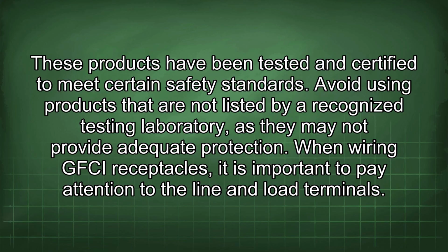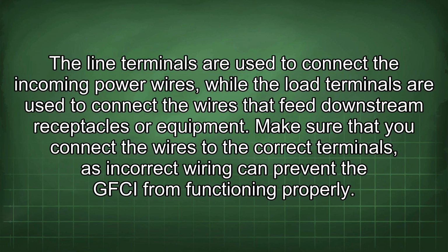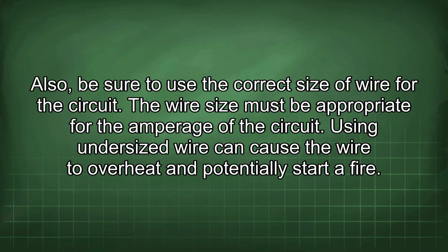When wiring GFCI receptacles, it is important to pay attention to the line and load terminals. The line terminals are used to connect the incoming power wires, while the load terminals are used to connect the wires that feed downstream receptacles or equipment. Make sure that you connect the wires to the correct terminals, as incorrect wiring can prevent the GFCI from functioning properly. Also, be sure to use the correct size of wire for the circuit. The wire size must be appropriate for the amperage of the circuit. Using undersized wire can cause the wire to overheat and potentially start a fire.